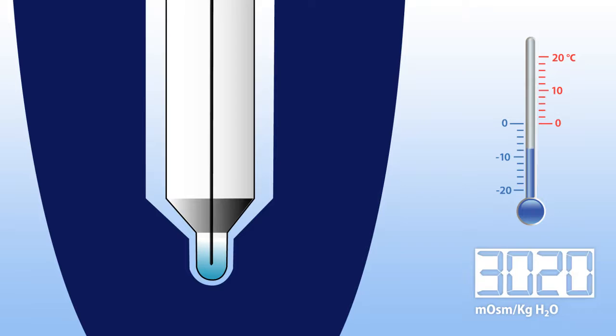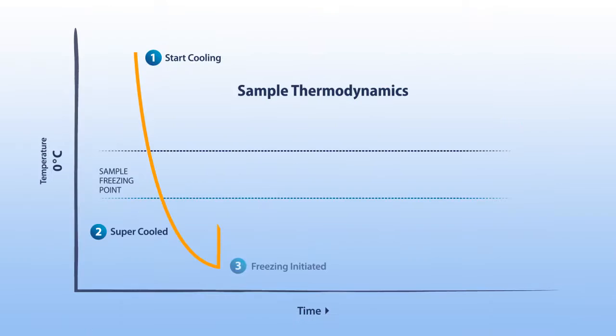This rate of cooling is tightly controlled by the osmometer. While the sample is in the supercooled state, a physical shock, called the freeze pulse, is introduced to the sample.